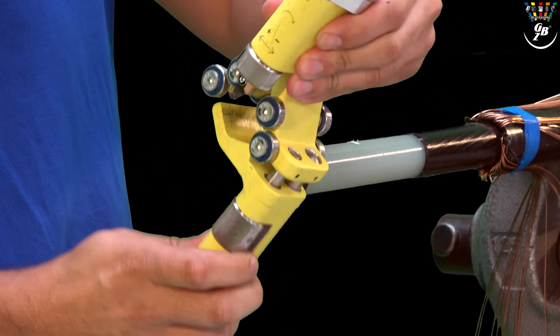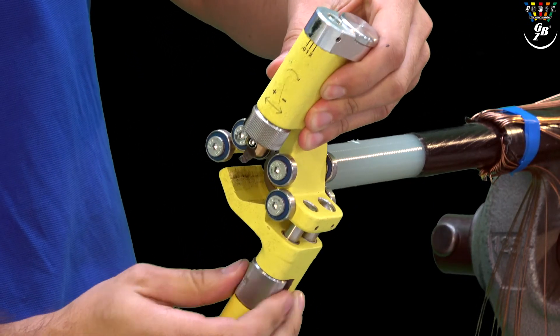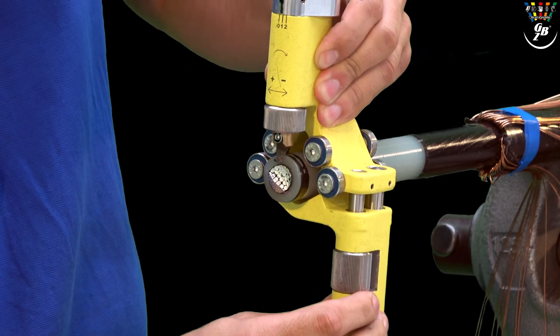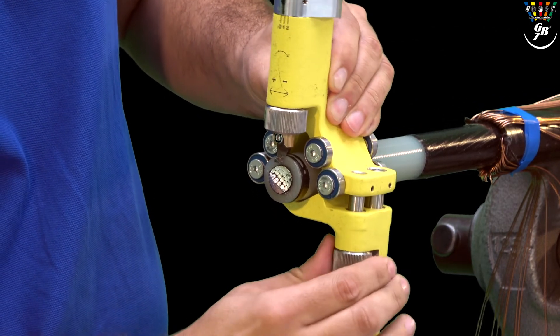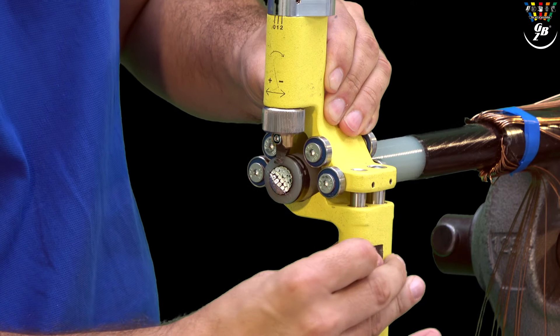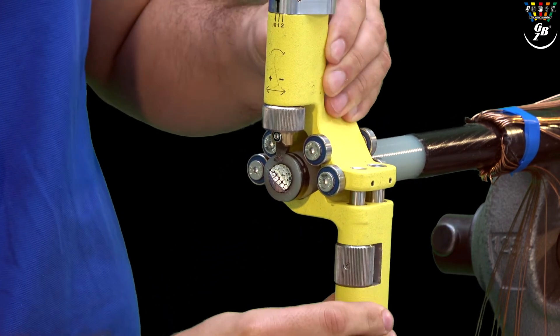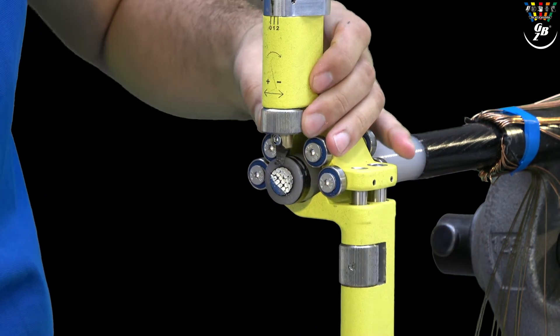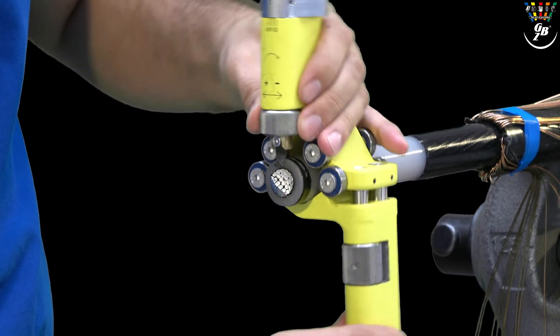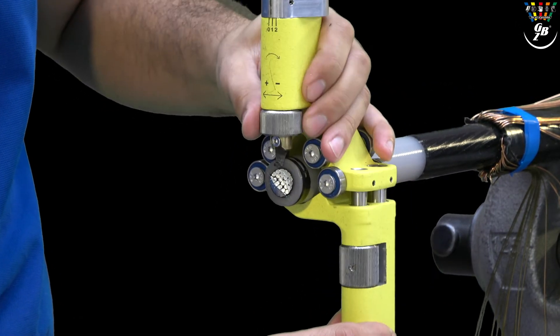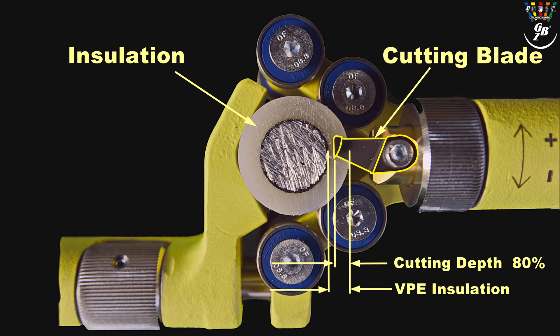The sheath cutter GBP20 will be mounted on the cable as in the first step and the cutting depth has to be adjusted. The blade is only adjusted to a cutting depth of approximately 80% of the insulation to avoid damaging the conductor.